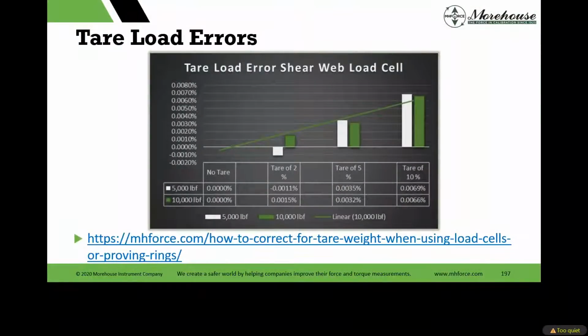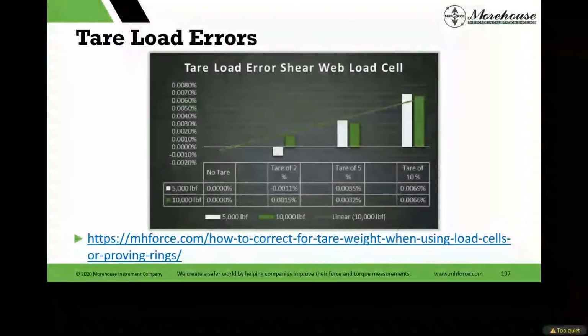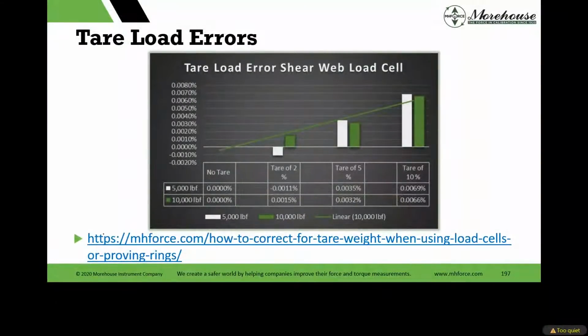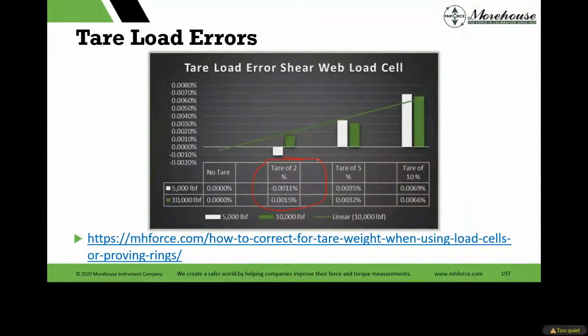Tare loads, if you have a Cal machine, I get this question a lot. How much Tare load? Some manufacturers will say 1% of capacity for the load cell. Some will say 2. I'm on the 2. Some of the testing I've done, if we look at this number, Tare of 2%, which basically means I have a 10,000 pound load cell and I put 200 pounds on it and push the Tare button. So it's like I stuck it in a machine.